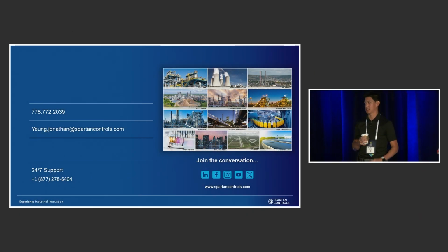Short answer is yes. All of that plays into how much momentum the fluid has, sometimes referred to as the Reynolds number, and that's really important when we do a sizing. Ideally we'd have some of those values. If we're just talking about water, we can pretty accurately understand what typical water viscosity is, or if you have an idea of the solids number, we can estimate it. But yeah, that would have an impact on accuracy for sure.